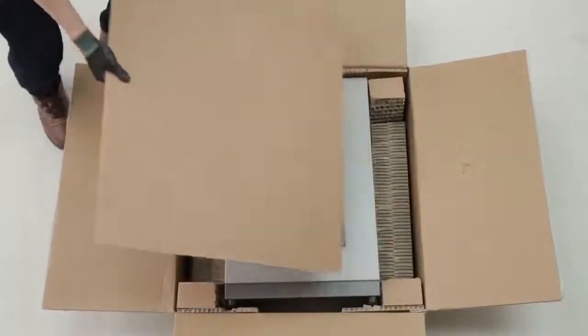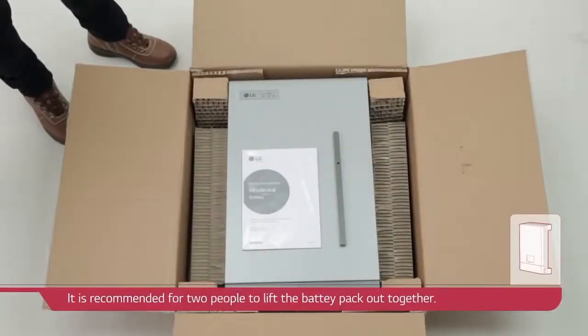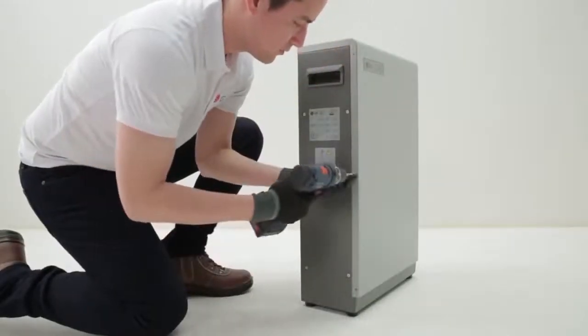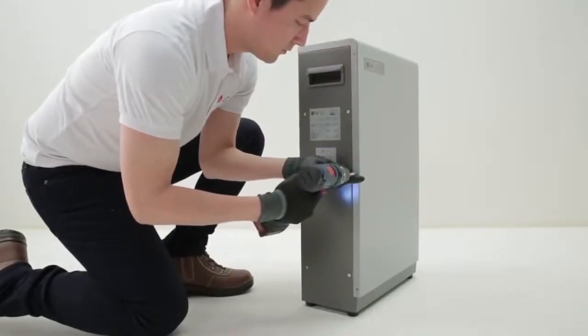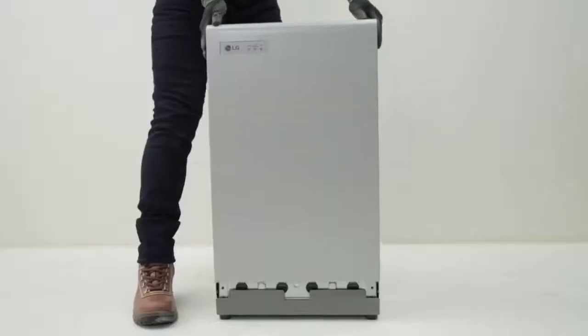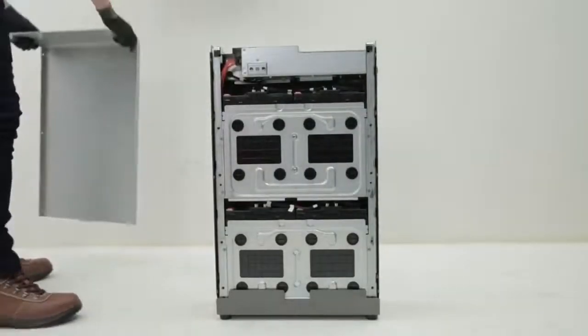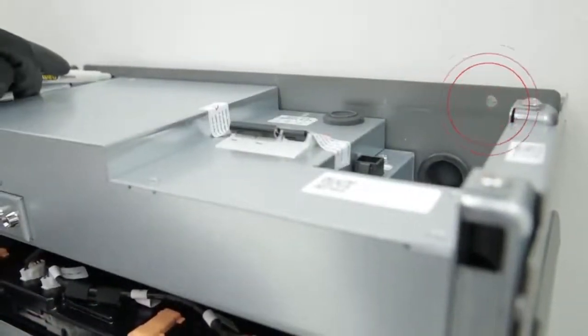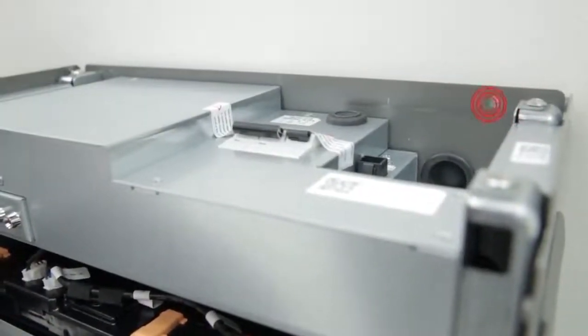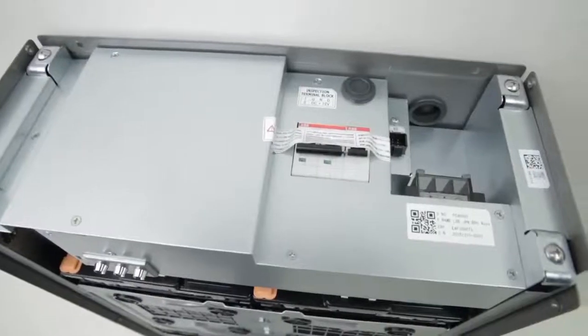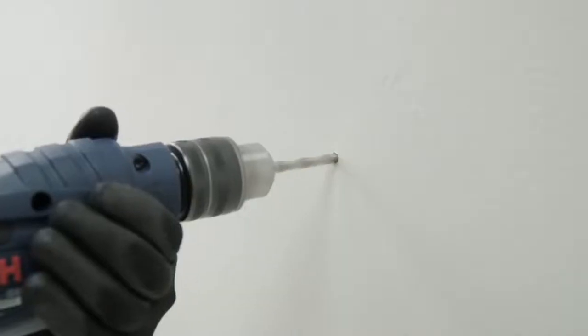Now, let's move on to the battery installation. Open the box of the battery system and lift it out carefully. It is recommended for 2 people to lift it out together. Loosen 8 screws in total on each side of the battery system in order to open the front cover. Disassemble the front cover slowly by sliding it up. Place the battery system against the wall first and mark the drill positions through the screw holes of the battery system. Move the battery aside from the marked position, drill holes on the indicated positions, and insert anchors into the holes.